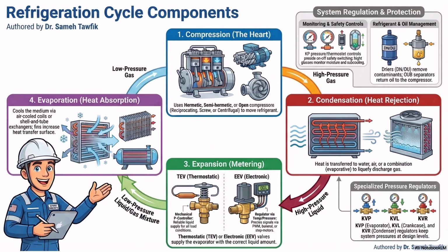Now, there's a really quirky, almost counterintuitive aha moment hidden in this section of the source material. Oh, the defrosting. Yes. It says that to ensure the evaporator keeps its capacity to cool the air, it actually has to be routinely defrosted. Wait, wouldn't a freezing cold, icy coil be exactly what you want to cool a room down? You would definitely think so. But if we connect this to the physics of the room, the paradox makes perfect sense.